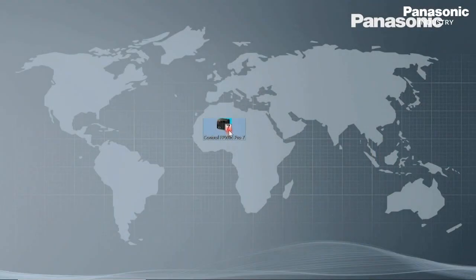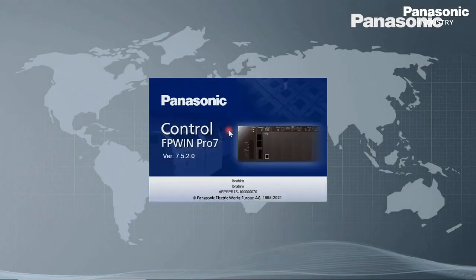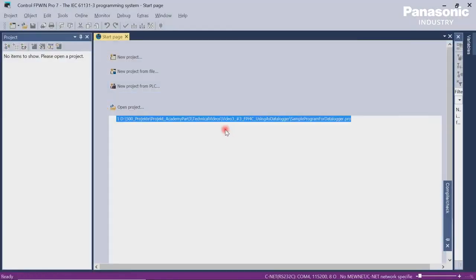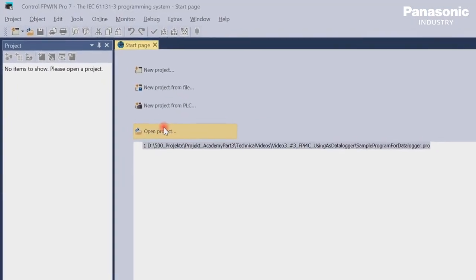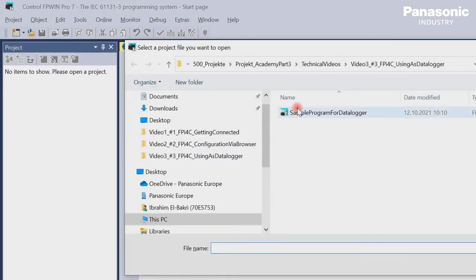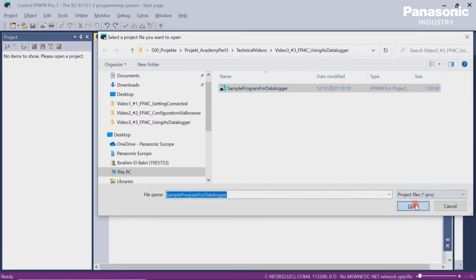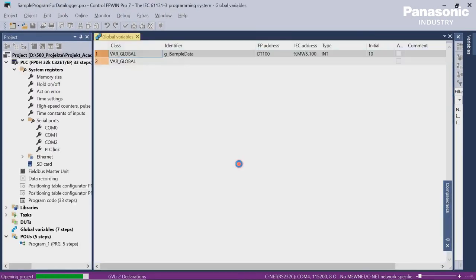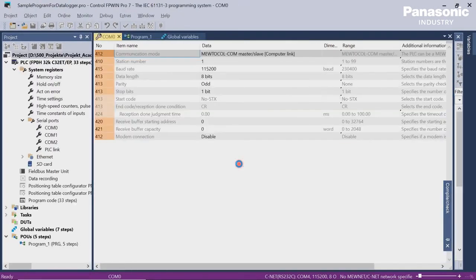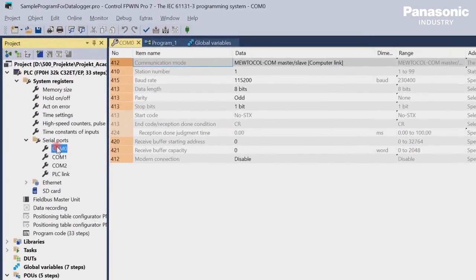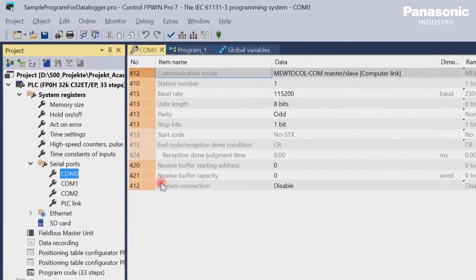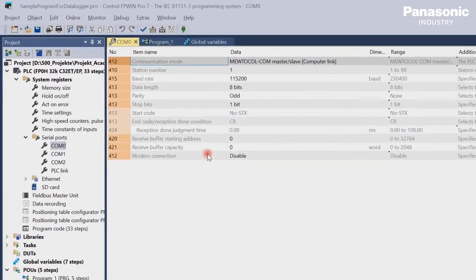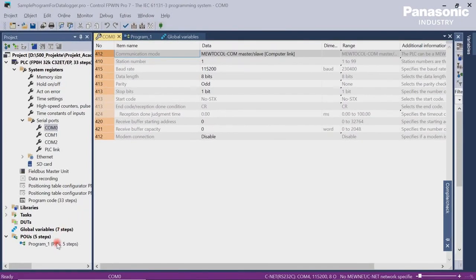Second step is to open our FPWinPro7 programming software in order to set the configuration parameters for the COM0 port on PLC side. Be aware that these configuration settings for COM0 port must be equal to the settings in the FPI4C unit later on.